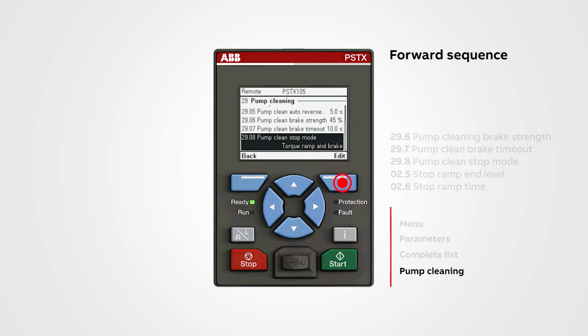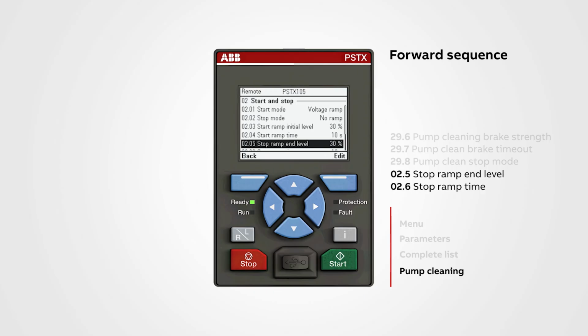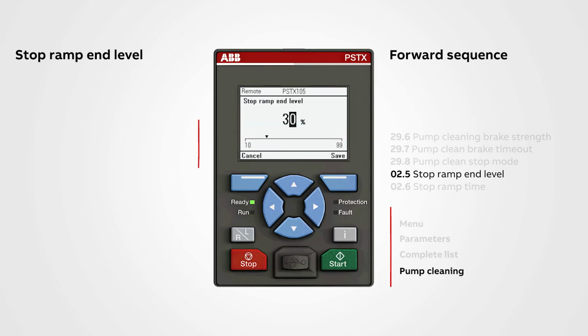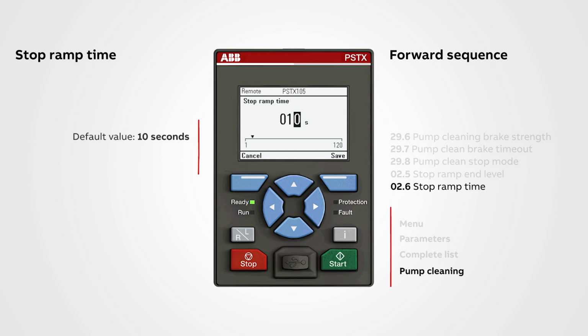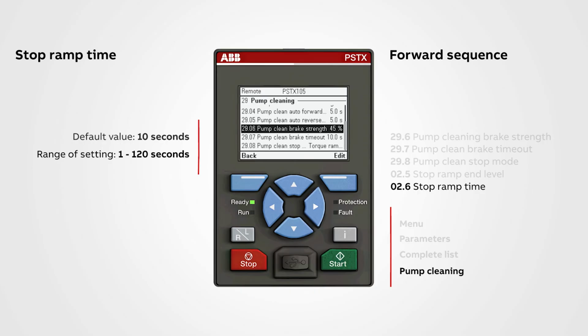For the alternative parameters 02.5 and 02.6 that are related to voltage or torque stop ramp end level, as well as the stop ramp time, these 2 parameters are located in Section 2, Start and Stop section. The parameter 02.5, stop ramp end level, has a default value of 30% and can be set between 10 to 99%. And the parameter 02.6, stop ramp time, has a default value of 10 seconds and can be set between 1 to 120 seconds. Now, let us return to Pump Cleaning Section 29 again and look at the last 2 parameters.